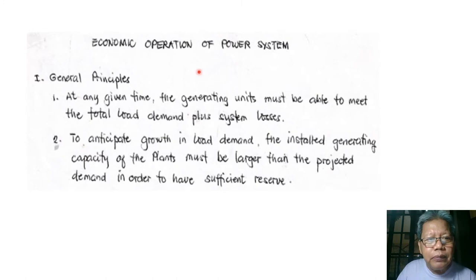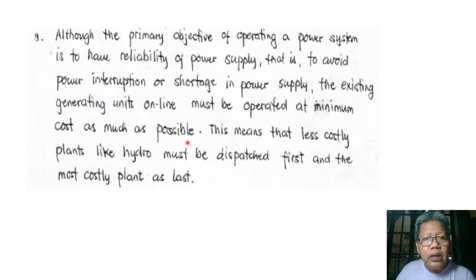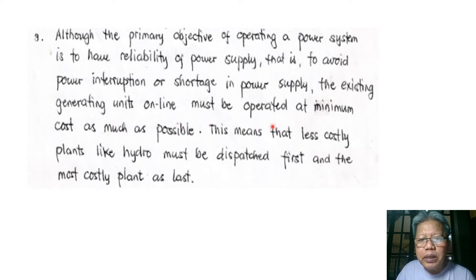We have to consider the general principles. Number one: at any given time, the generating units must be able to meet the total load demand plus system losses. Second: to anticipate growth in load demand, the installed generating capacity must be larger than the projected demand. Third: although the primary objective is reliability of power supply — to avoid interruption or shortage — the existing generating units must be operated at minimum cost as much as possible. This means less costly plants like hydro must be dispatched first, and the most costly plants like diesel last.